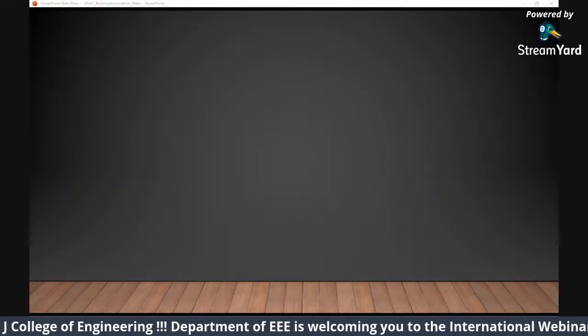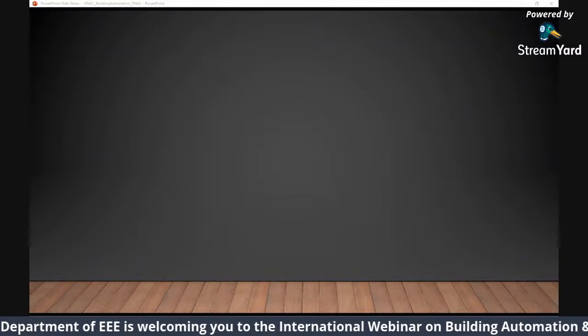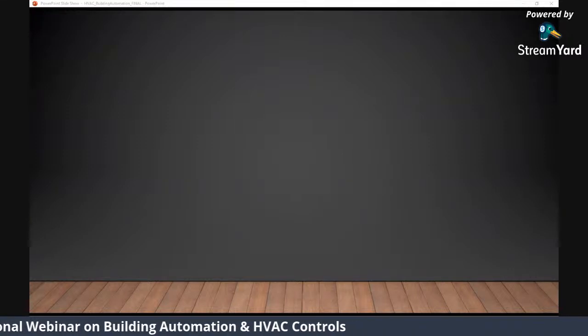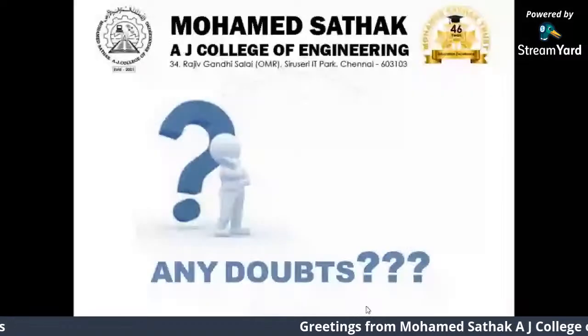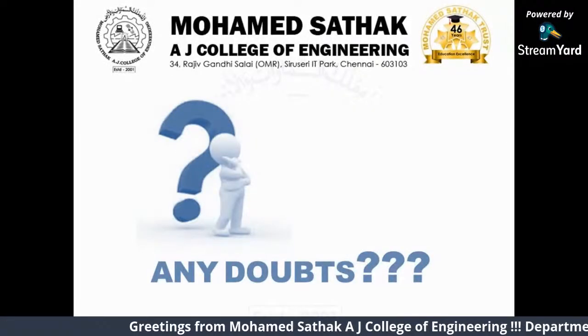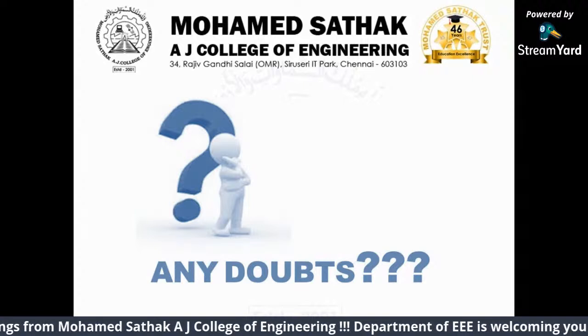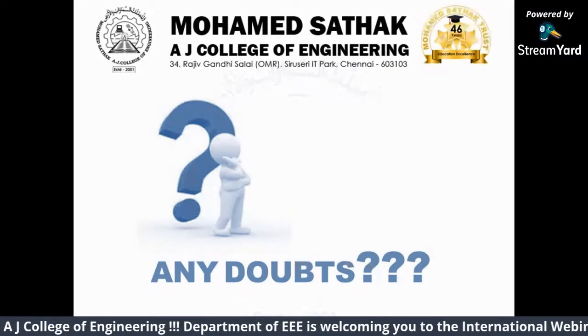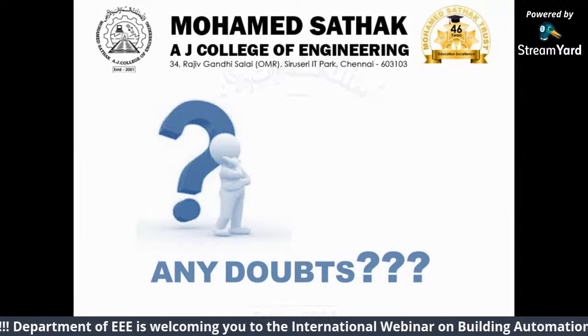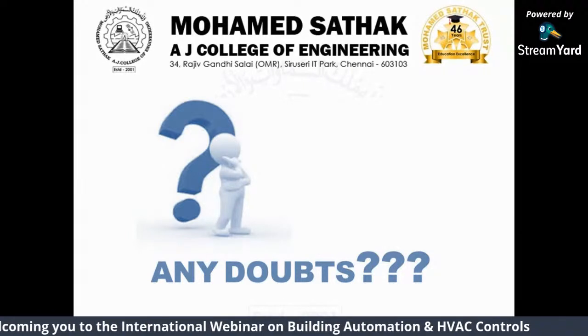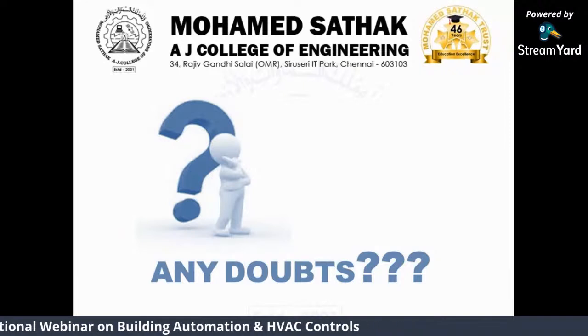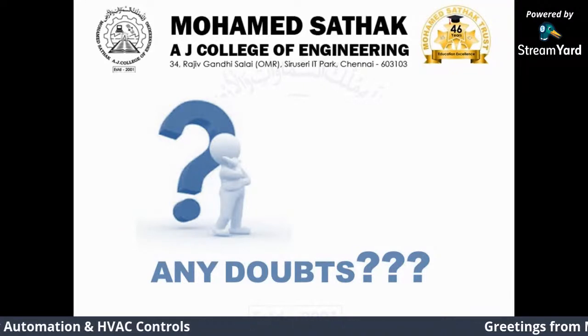What was the other question? The damper MOV is on and off for 4-20 control. The damper, again, depends on the equipment, depends on the purpose. Let's say it is an exhaust fan. All you have to do is just turn it on and off. You don't have to control your exhaust fan. There will be a damper for your exhaust fan. All you have to do is turn the fan on and off. And if it's an outside damper or return damper, you will modulate them 4 to 20, 2 to 10, or 0 to 10. It depends on the purpose. If it's outside dampers or valves, it's a modulating signal, 0 to 10, 4 to 20. If it's just two position, it depends on it.